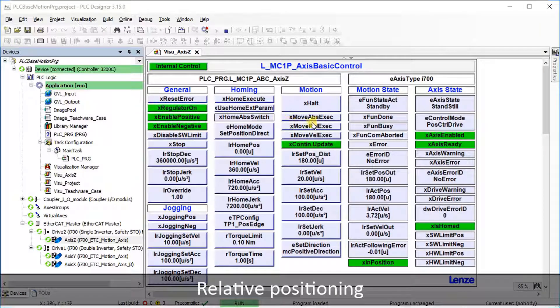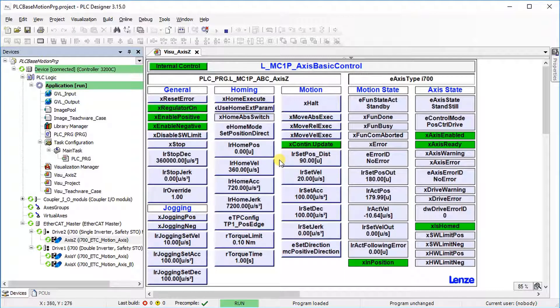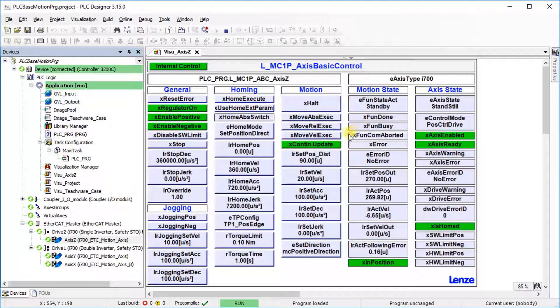Relative positioning is also possible through the visualization. In the case of relative positioning, the target position defined in the set position distance input corresponds to the distance to be traveled, meaning that the drive exactly travels the distance defined from the current actual position. The axis should be enabled. A travel to the relative target position in the set position distance input starts on the basis of the parameter in the motion profile. Assign a rising edge to the move relative execute input. The technology module changes to move relative state. The function remains busy until the position is reached. The in position output is set to true after the target position was reached. When the target position has been reached, the axis is brought to standstill by using the deceleration parameter.